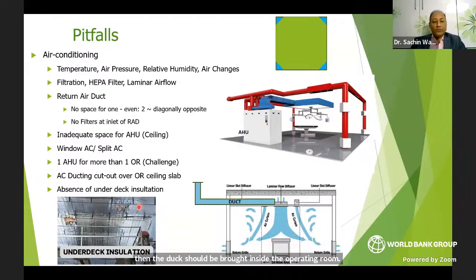One more thing we could do is insulate the ceiling slab, because the ceiling also sheds a lot of particles. The second point is that so much cold air in the operating room leads to sweating, and that leads to dripping.